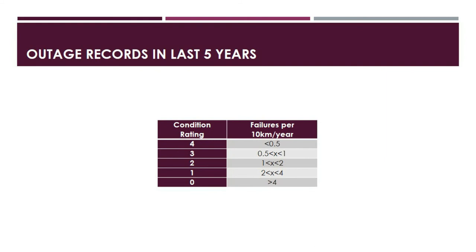The fifth category is outage records in the last 5 years, based on failures per 10 kilometers of cable per year. Rating 4 is less than 0.5 failures. Rating 3 is between 0.5 and 1. Rating 2 is between 1 and 2—the cable is deteriorating. Rating 1 is between 2 and 4—the cable is close to end of life. Rating 0 is greater than 4 failures—the cable is at end of life.